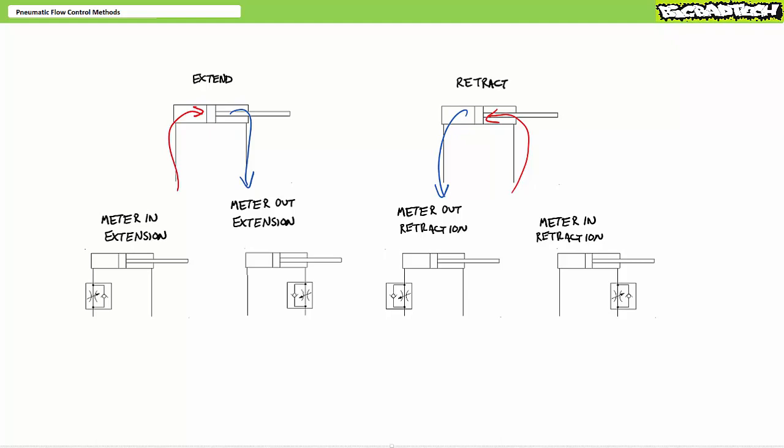As easy as this general concept may be, the difficulty in implementing these four different methods is installing a flow control valve with check valve bypass in the proper location and the proper orientation. You'd be surprised how often people mess this up under stress. My advice: pay attention to the check valve, since it is the single component that determines the restricted and unrestricted directional flow. Let's examine all four methods starting with meter in extension.